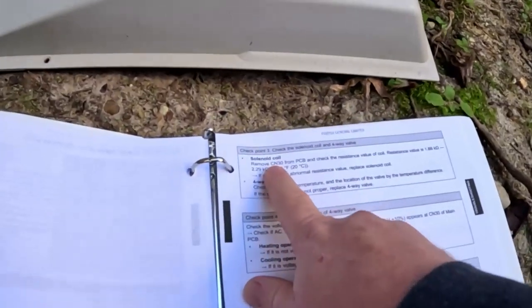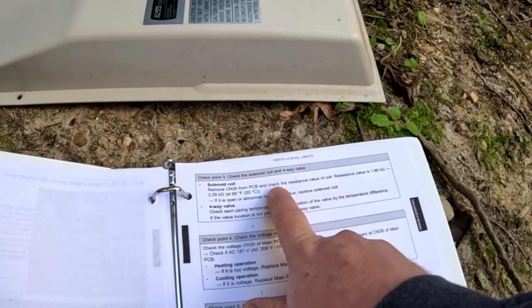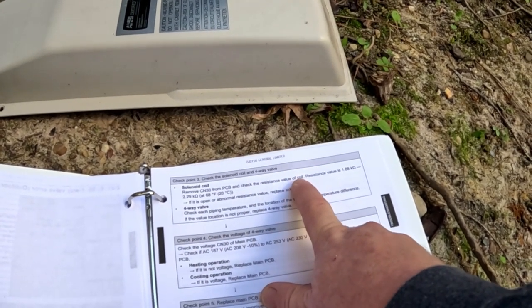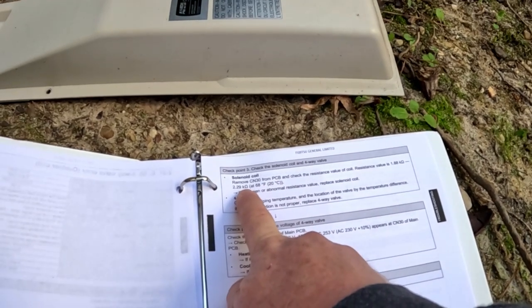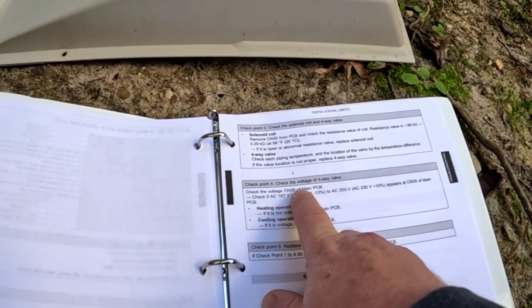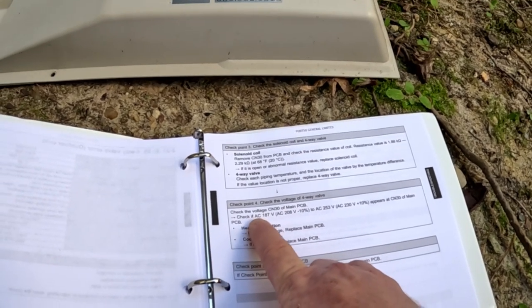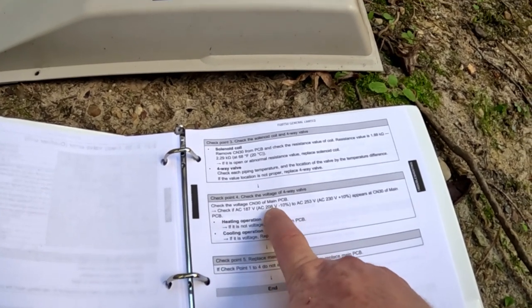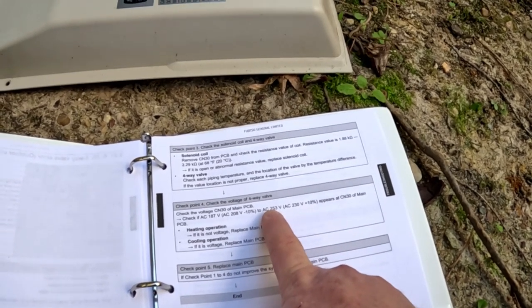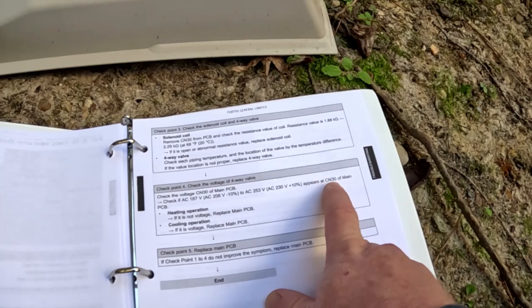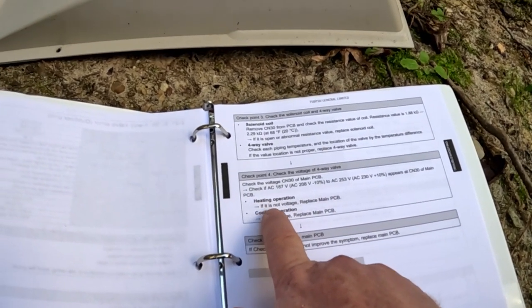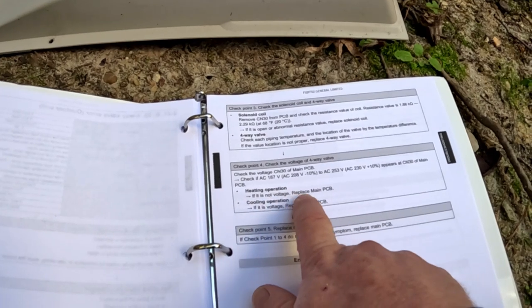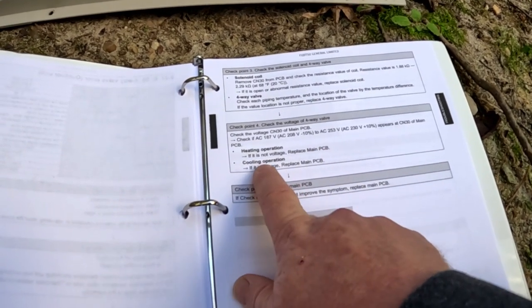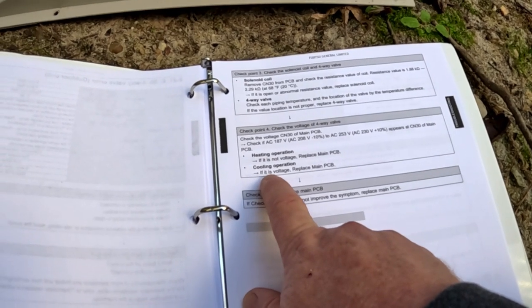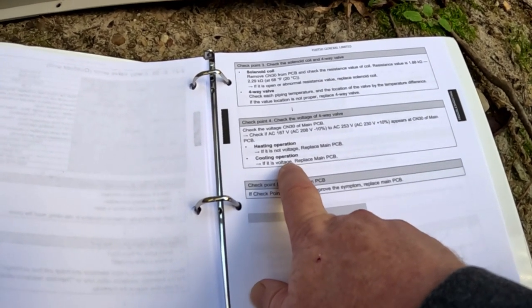It says remove the CN30 from the board. Check the resistance value on the coil. And at the same terminal, check if your AC voltage, depending on whether you got 208, 230, is 187 to 253 volts, appears at the main PCB. If not present in heating operation, replace the main PCB. If it does have voltage in cooling mode, replace the main PCB.